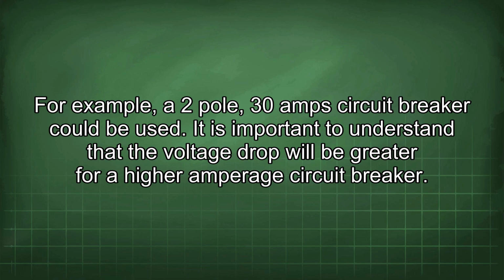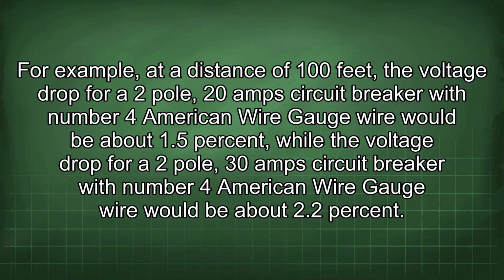It is important to understand that the voltage drop will be greater for a higher amperage circuit breaker. For example, at a distance of 100 feet, the voltage drop for a 2-pole 20-amp circuit breaker with number 4 American wire gauge wire would be about 1.5%, while the voltage drop for a 2-pole 30-amp circuit breaker with number 4 American wire gauge wire would be about 2.2%.